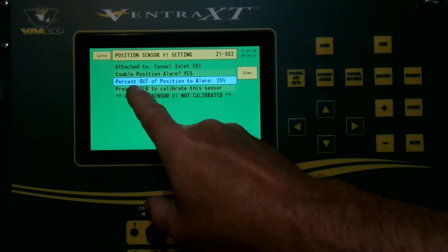You can set it for 15% or 30% or 5%, whatever you would like, but you don't want to set it too tight because you might get nuisance alarms if you try to do that. But 10 to 25%, probably anywhere in there would be a good starting point, but again, that's up to you on how you would like to set your system.